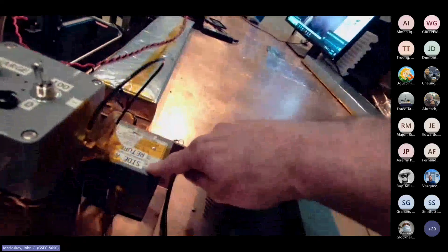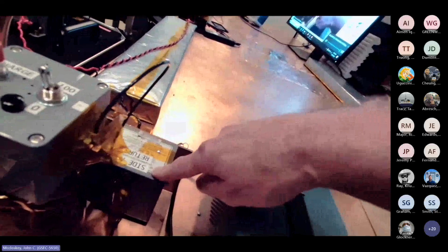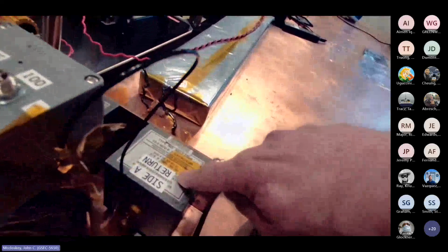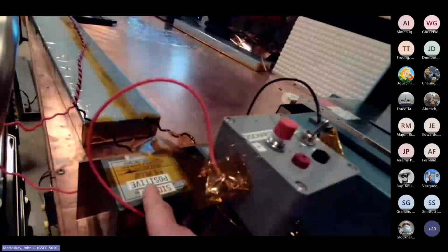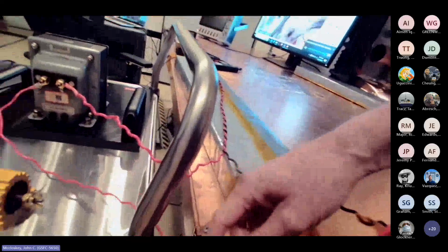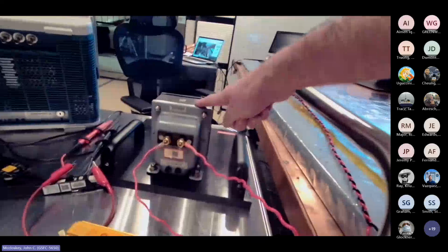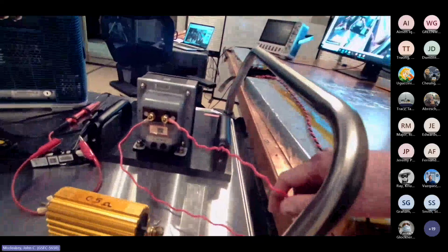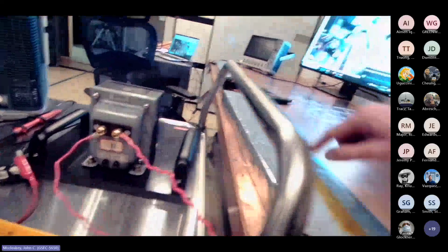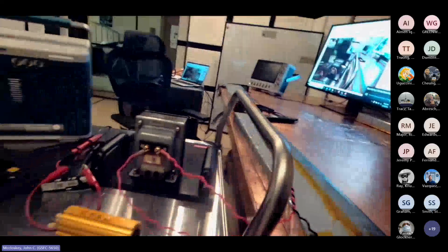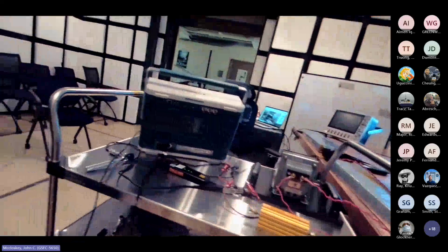Black wire is marked side A return. That's from probably an earlier test when we were doing side A and side B, right? But the important thing is return. And the red wire is going to positive, going to the red wire on the other side. Then the red wire is going to our transformer. And then the other terminal is going to the EUT, which is our power converter.